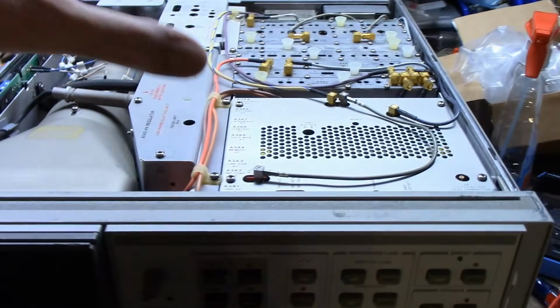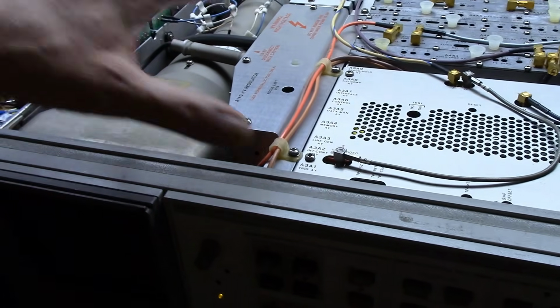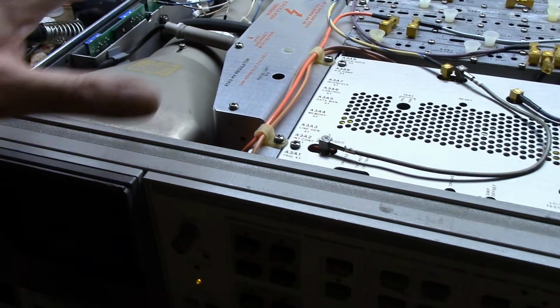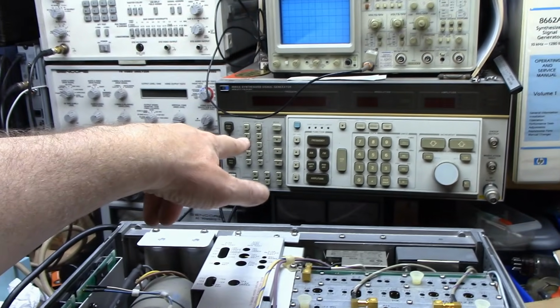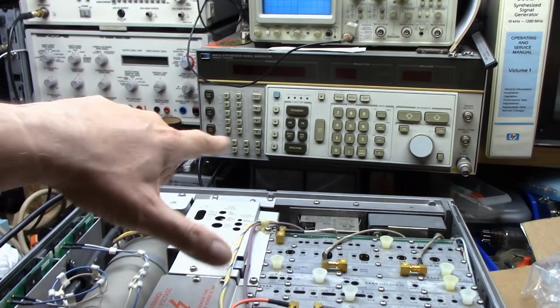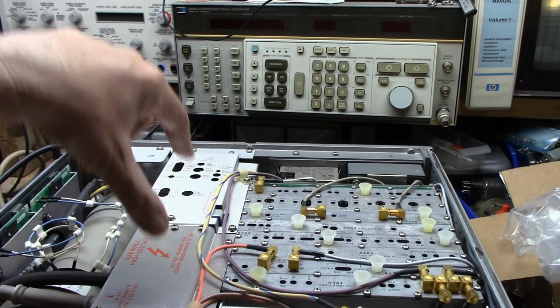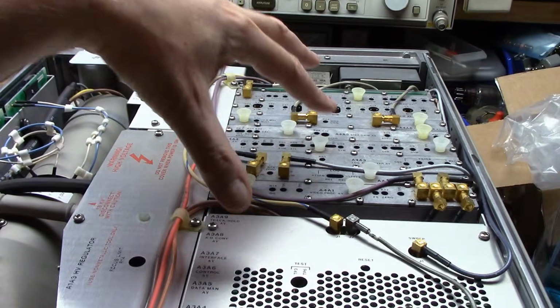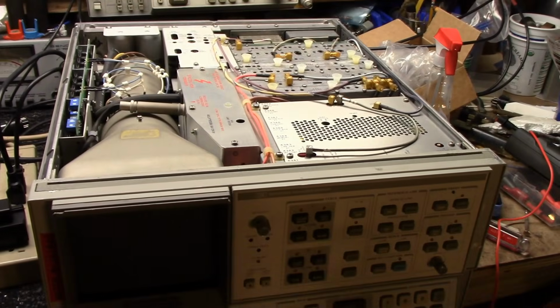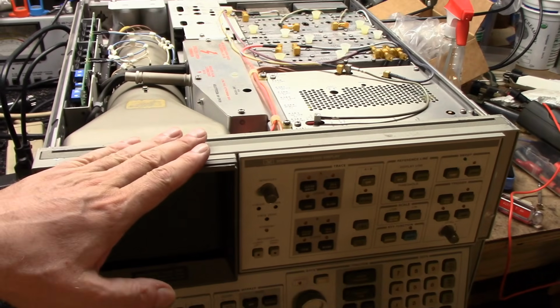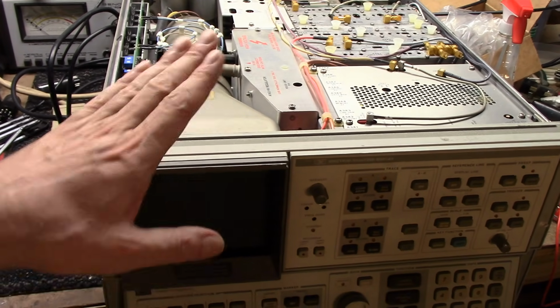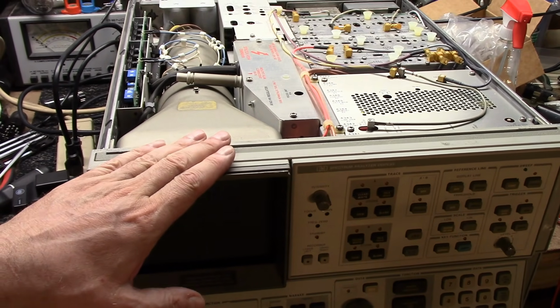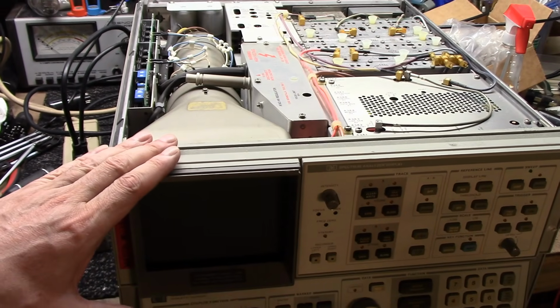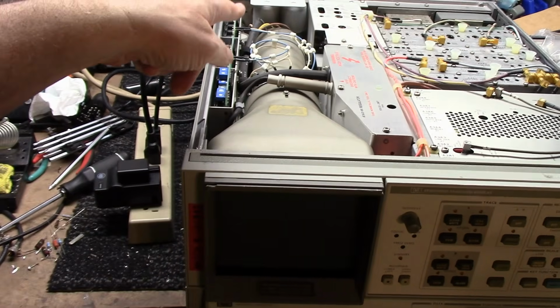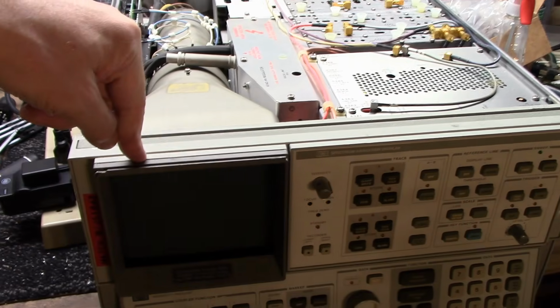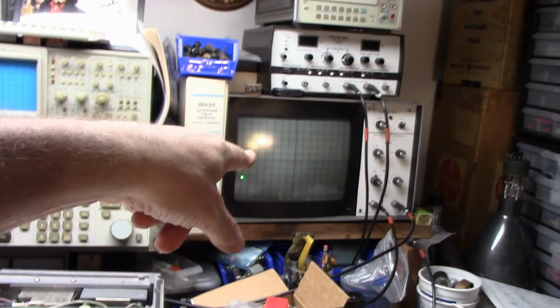It's very modular. In general, their service info from this era is very good. It certainly helped me get my 8662A fixed. They had troubleshooting charts, schematics, things to check. It should be very similar for this device. Yes, the service info for this device is excellent. One of the first troubleshooting things they say to do if you have a blank display is check the external outputs. We have XYZ on the output of this. It's a vector display in here. So I have it now going to my WaveTech 1901.